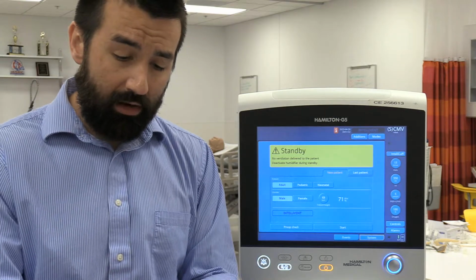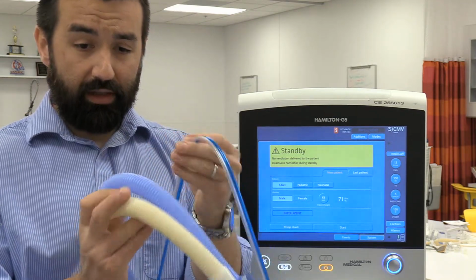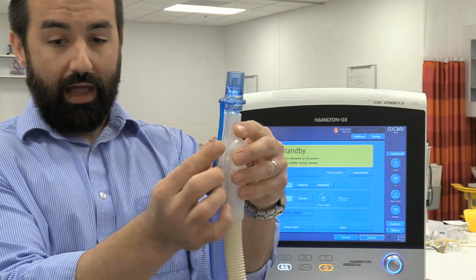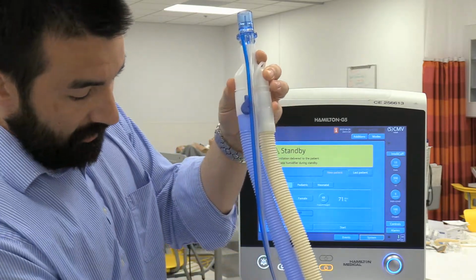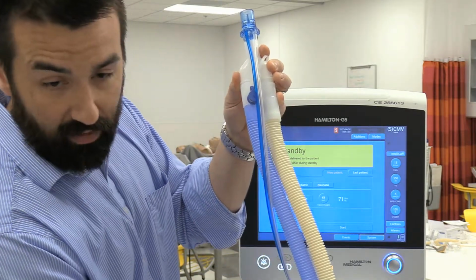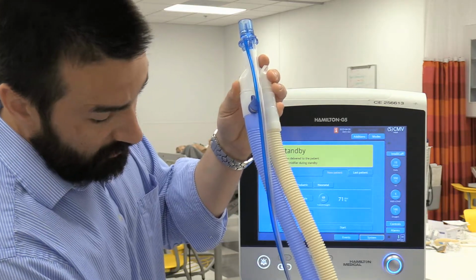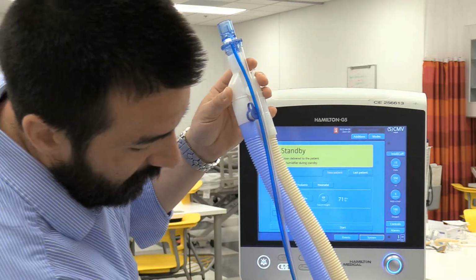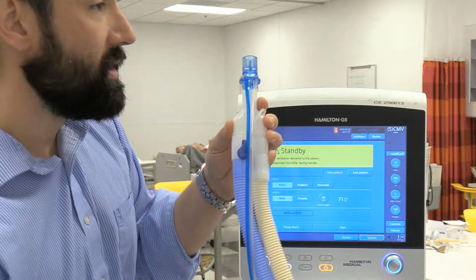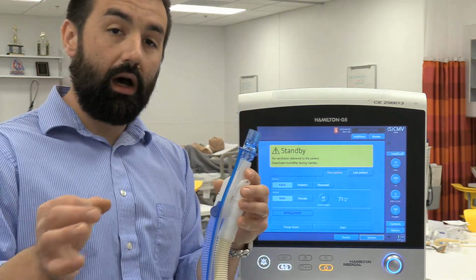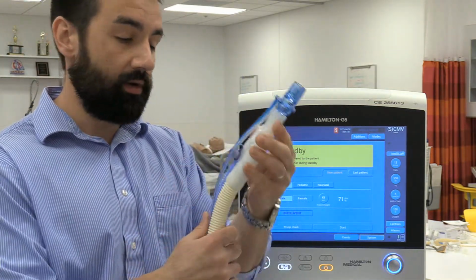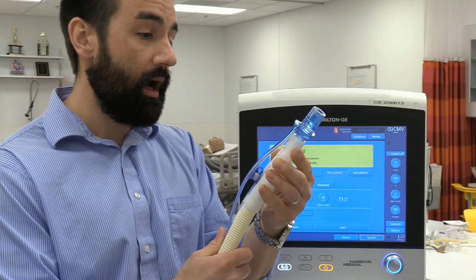I'm not going to zoom back out and show you where to hook this up to the ventilator, but you can see there are two separate colored lines that need to be tied back in at the ventilator. On the very bottom right here, our particular one has about 5 different little hookups. A couple are labeled flow sensor, and you'll see there's a color-coded shroud up above them that coincides with the color on the flow sensor. So make sure you get that set back up.